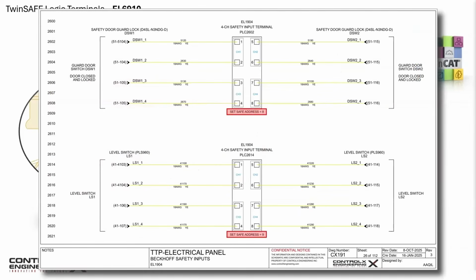Personally, I always specify the FSoE addresses of the TwinSAFE terminals in the electrical design schematics. This way, the terminal gets the address set during the panel build process. During software commissioning, these addresses have to be validated in TwinSAFE, which we'll see in the next part of this tutorial.